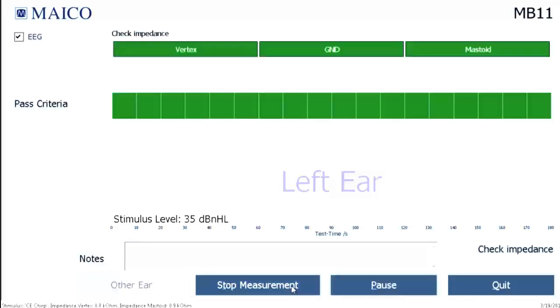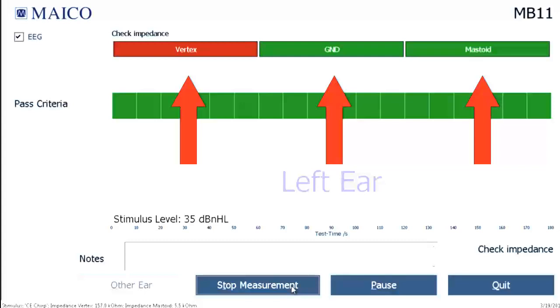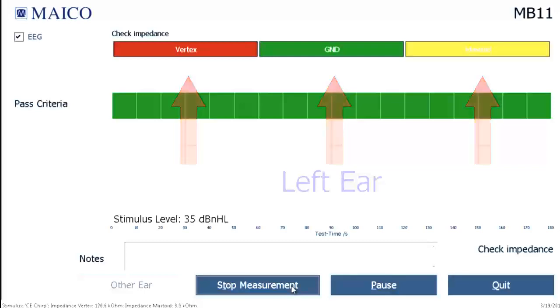When a screening is started, the quality of the contact of the electrodes to the skin, referred to as the impedance, is checked. Feedback is shown on the top of the screen with 3 traffic lights, one for each electrode. When all 3 traffic lights remain yellow or green for several seconds, the ABR data collection will begin automatically. If any of the traffic lights shows solid or flashing red, then this electrode does not have good contact with the baby's skin. You'll need to resolve the problem before the data collection will begin. Please see the chapter on troubleshooting tips.